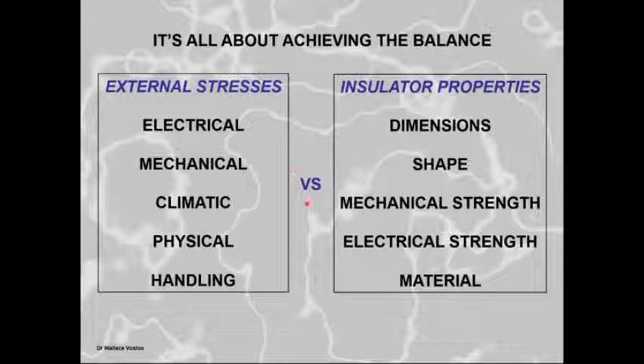Now, we need to balance that up by selecting insulators and selecting the properties of insulators that will counteract these TOVs and the actual pollution and things like mechanical stresses. And to counteract that, we need to make certain that when we choose an insulator, the dimensions of the insulator are chosen so that it can fit within the tower geometries and so on, and will actually help to counteract these stresses. The shape of the insulator, whether it is an open aerodynamic profile or a deep under-rib profile, all helps for different situations when it comes to the stresses. Your mechanical strength of the insulator you must select accordingly, as well as your electrical strength to be able to handle these stresses. And obviously the type of material.